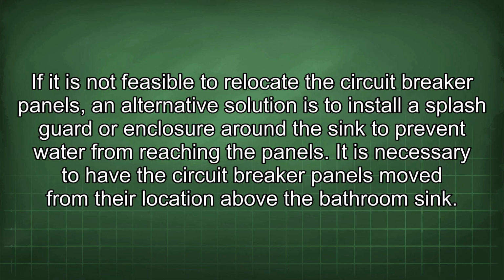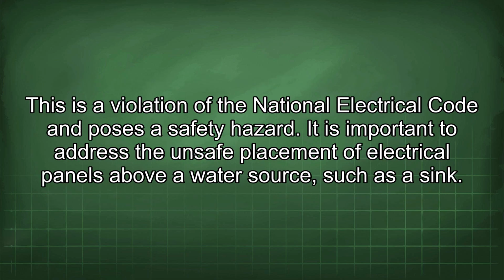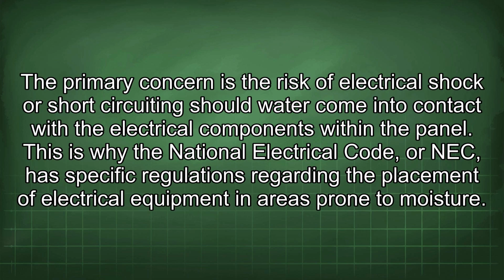It is necessary to have the circuit breaker panels moved from their location above the bathroom sink. This is a violation of the National Electrical Code and poses a safety hazard. It is important to address the unsafe placement of electrical panels above a water source, such as the sink. The primary concern is the risk of electrical shock or short-circuiting should water come into contact with the electrical components within the panel. This is why the National Electrical Code, or NEC, has specific regulations regarding the placement of electrical equipment in areas prone to moisture.